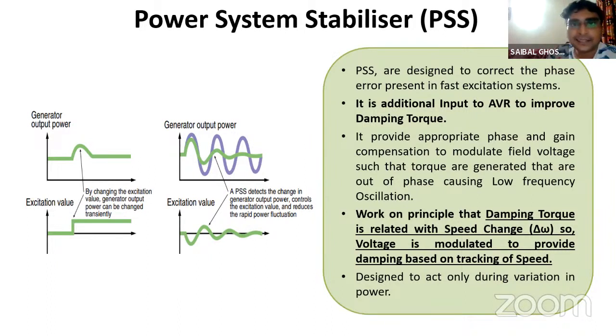Some PSS can just sense the speed, and based on speed it can operate. That means the generator speed acts as an input. Sometimes generated electrical power acts as an input to the PSS, and nowadays PSS2B, PSS2A are dual input, where both speed and power are used. Using that complex PSS structure, we basically try to rebuild what is the accelerating power, and based on that accelerating power, we modulate the excitation voltage in phase with that accelerating power.